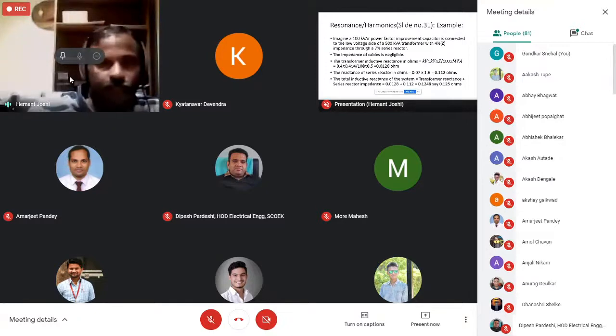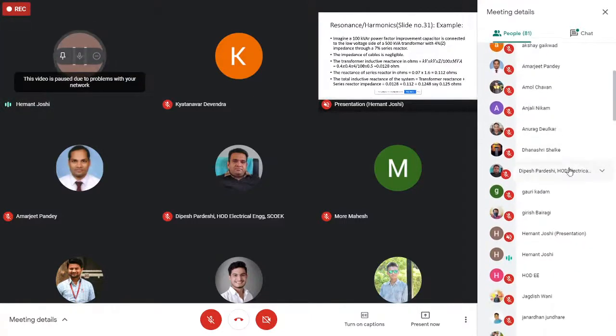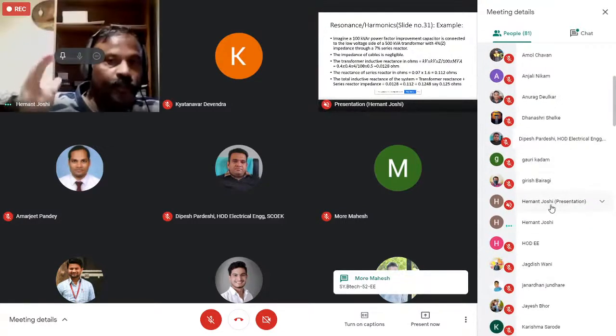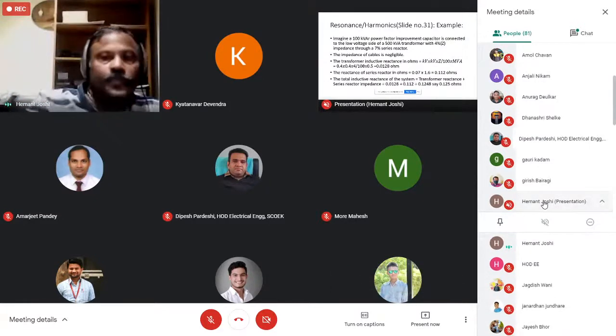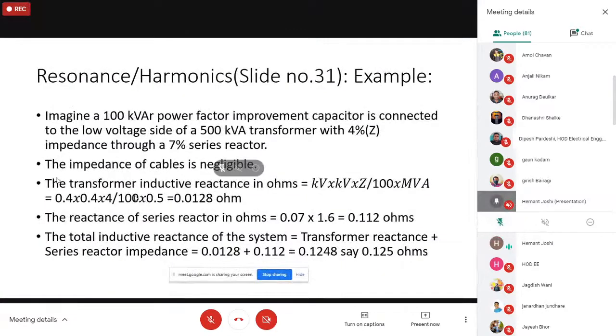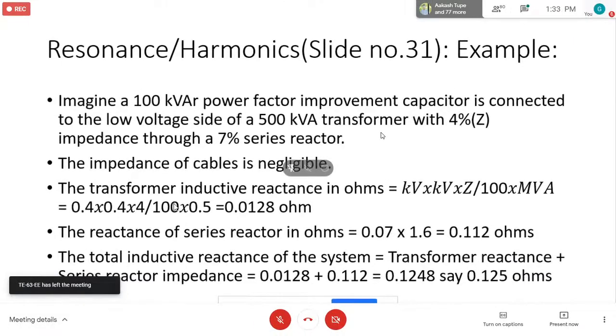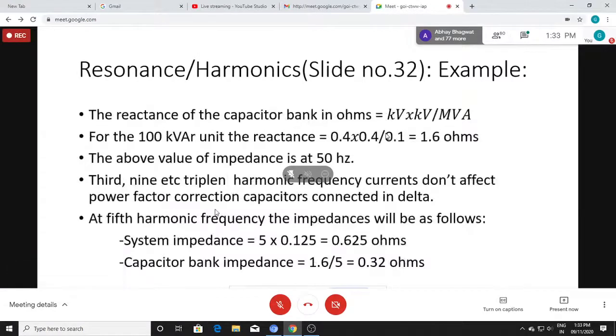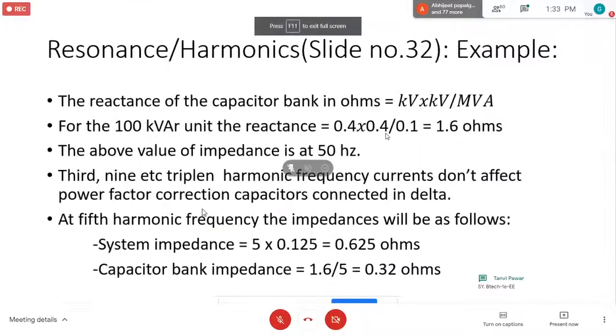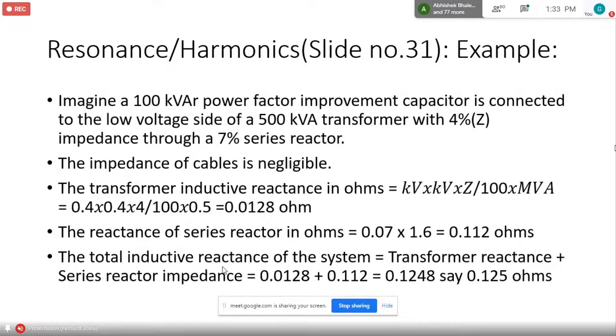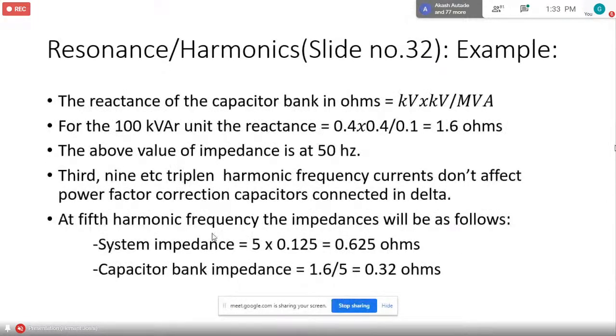I hope you know all these equations. Otherwise go and check your books. Whatever you are studying in the university, in your institute, don't forget, you will be applying in practice. The total inductive reactance of the system equals transformer reactance plus series reactor impedance: 0.0128 plus 0.112 equals 0.1248, say 0.125 ohms. The reactance of the capacitor bank in ohms is equal to kV square upon MVA. For 100 kVAR unit, the reactance is 1.6 ohms. That's why we had here 1.6 times 0.07, sorry. The above value of impedance is at 50 Hertz.